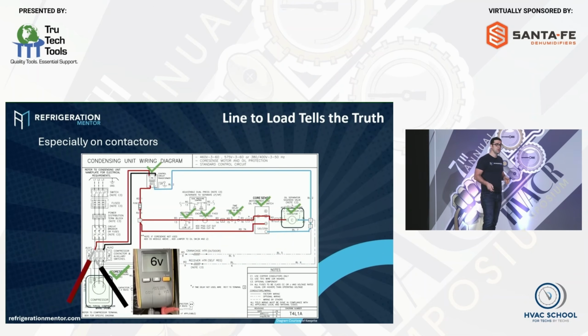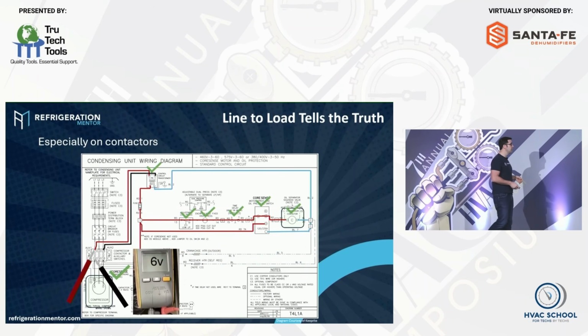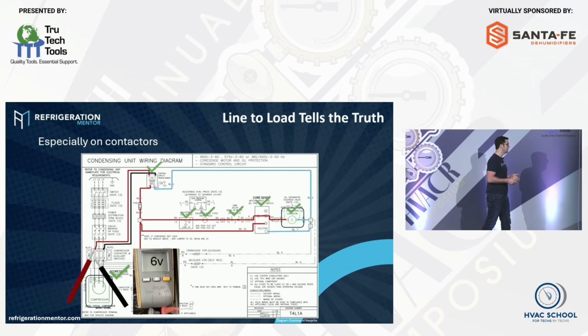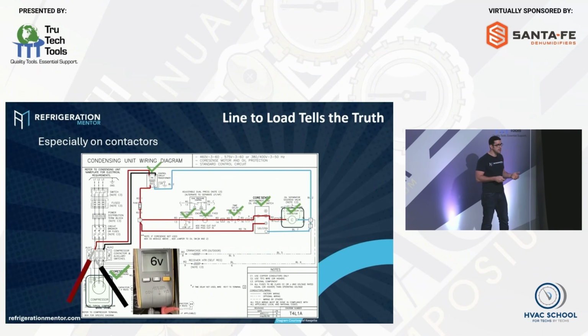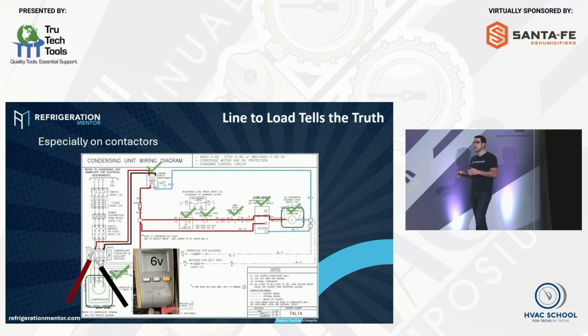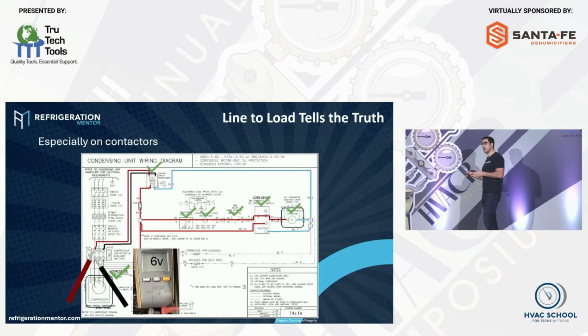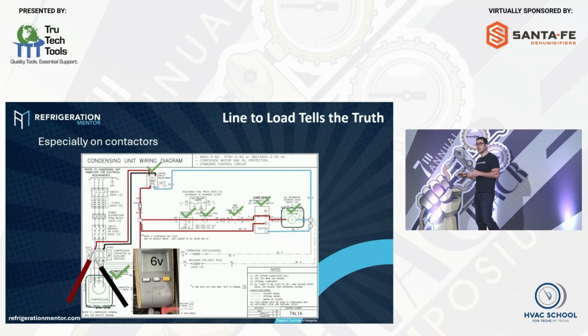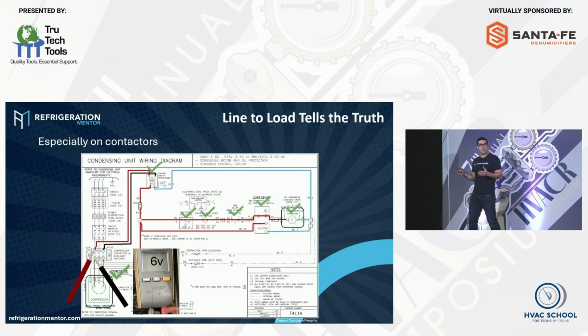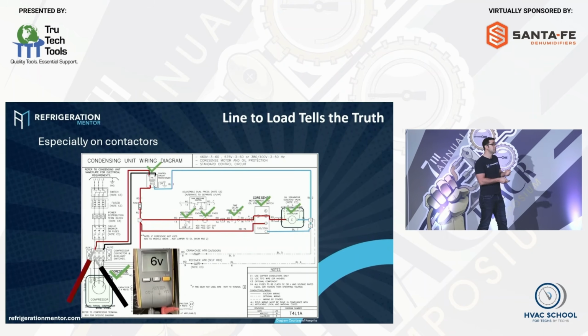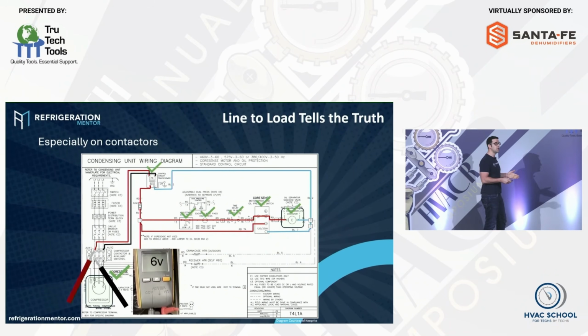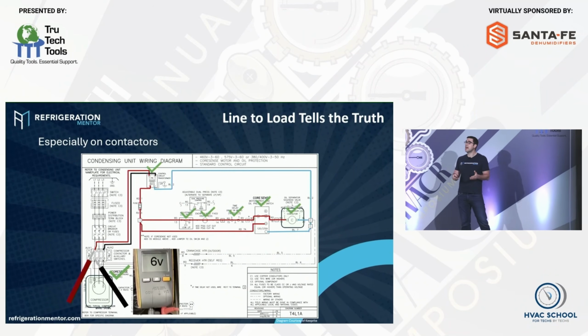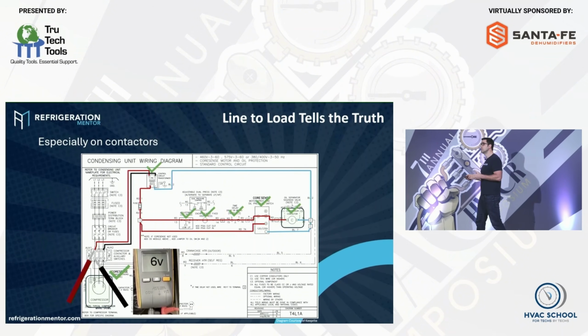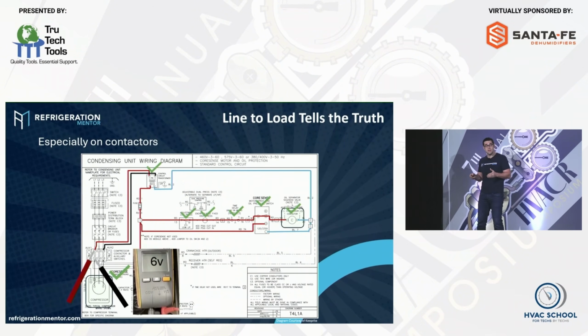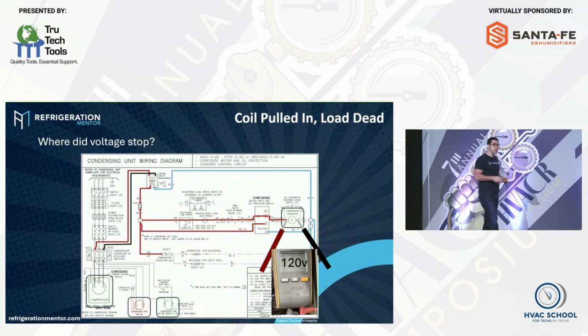The next step is line to load tells the truth. Why do we do this? Especially in contactors, this is so, so important in maintenance. You can really find out if contactors are bad or good with your meter, and a thermal imaging gun is very, very good too. But with your meter, you go across it, and you should get zero potential because it's closed. If you get 6 volts, 10 volts, there's a voltage drop, and that is probably some sort of pitting or dirt in those contactors. You really want to step that up and make sure.